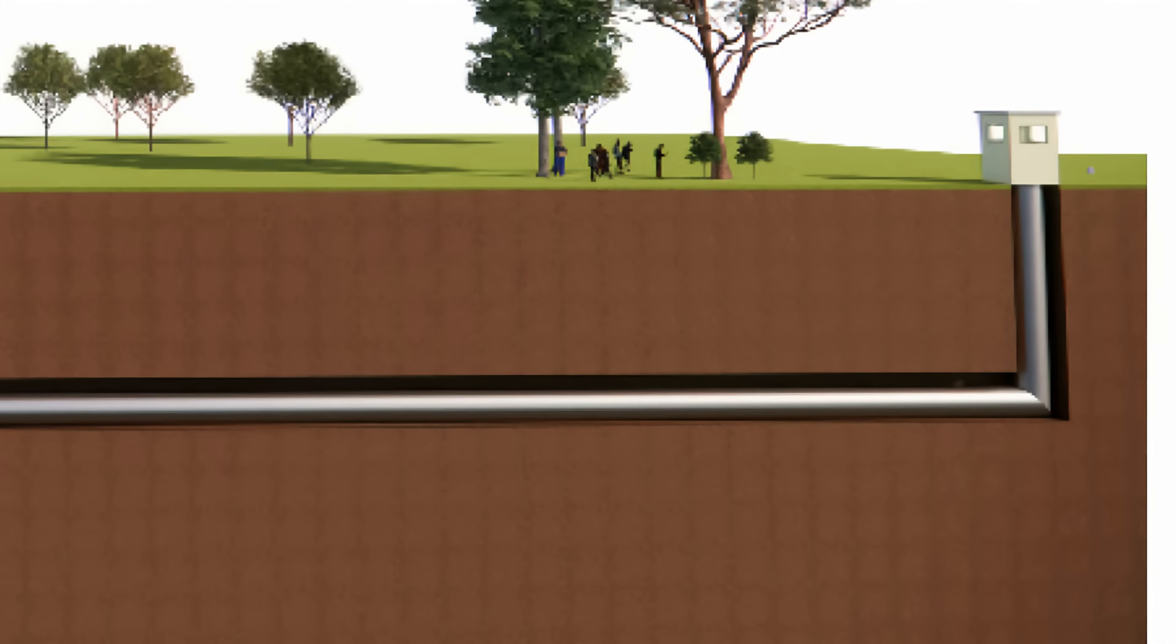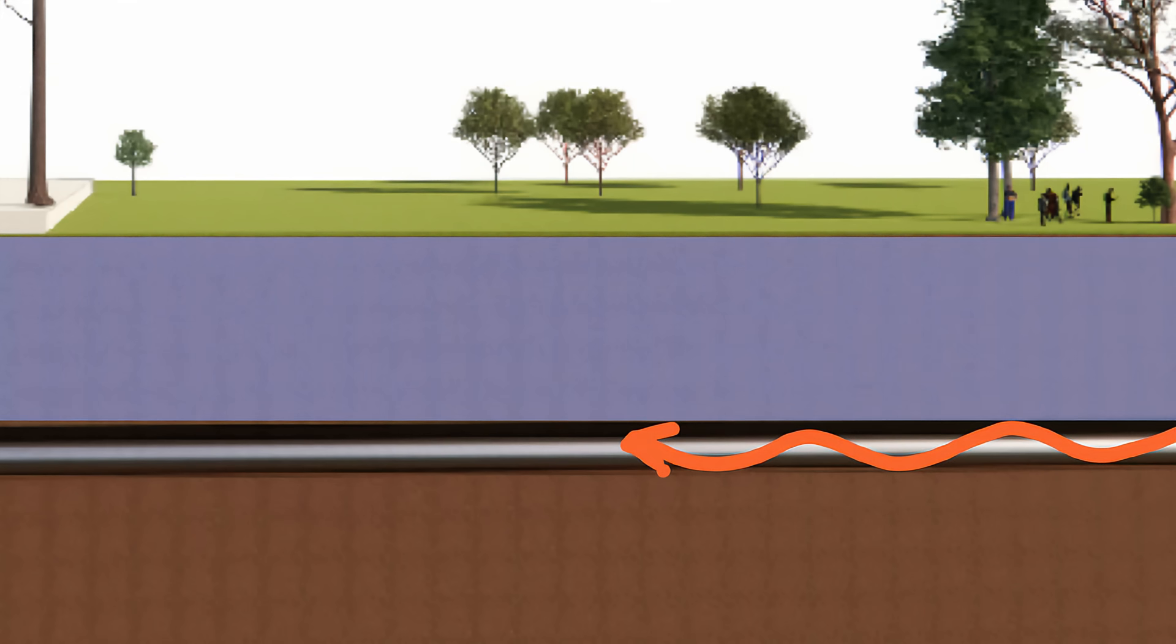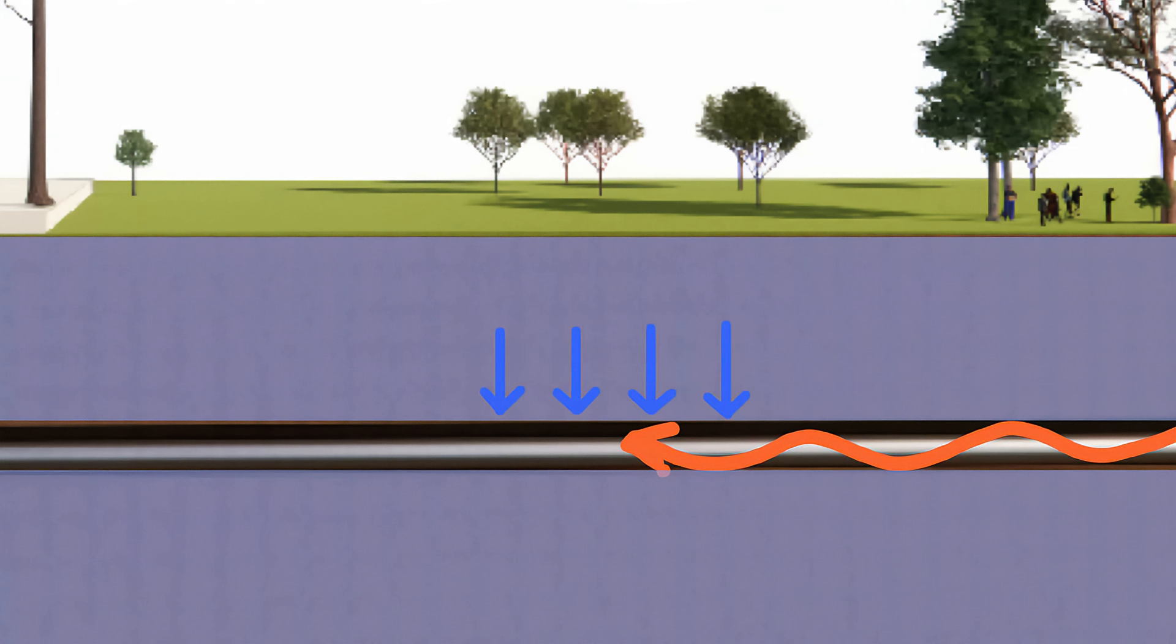The air then travels through a network of underground pipes buried 1.5 to 3 meters deep. As air moves through the underground pipes, heat is transferred between the air and the surrounding soil. The longer the air stays underground, the more it adjusts to the soil temperature.